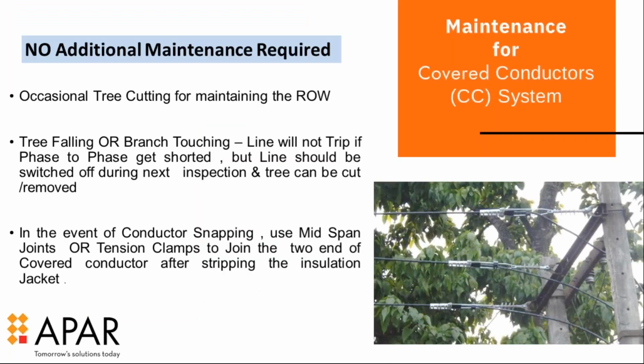So in the case of the covered conductor, no additional maintenance is required. Only occasional tree cutting for the maintenance of the ROW is recommended, because even if the tree branches are constantly touching the surface, that can be tolerated, but it should not be touched for a very long period. 2-3 months it is there, it's okay. But after 2-3 months, there should be some kind of maintenance to cut all the branches which are constantly touching the line.